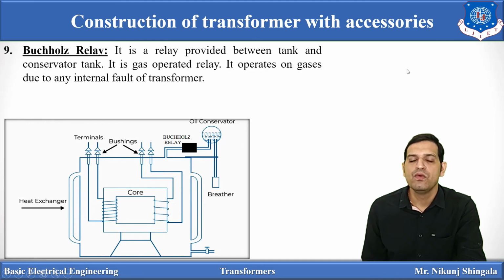Next one is the Buchholz relay. Here you can see one relay between the oil conservator tank and main tank. It is basically to protect the tank from internal fault. It is a gas operated relay. It operates on the gases produced due to any internal fault of the transformer. If any internal fault is there in the transformer, then oil gets burnt and because of this gases are produced. So it is a gas actuated relay or gas operated relay.